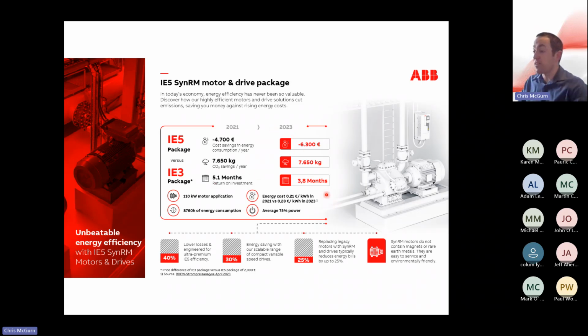In 2023, because of the shift in energy prices, and the fact that energy prices have gone up and up, that's gone even further. The return on investment you would actually see is 3.8 months. So because of the changes in energy prices, there are significant savings to be made by moving over to an IE5 package. Although you have to consider the initial outlay for buying the most efficient technology, it's important to understand that through the lifetime of that motor, you will see savings, and it should certainly be considered, especially for any greenfield projects that you want to meet modern efficiencies and then some. So like I say, you're talking 40% lower losses than IE3, and 30% energy saving with our variable speed drives. It's the way to go on any modern application out there.